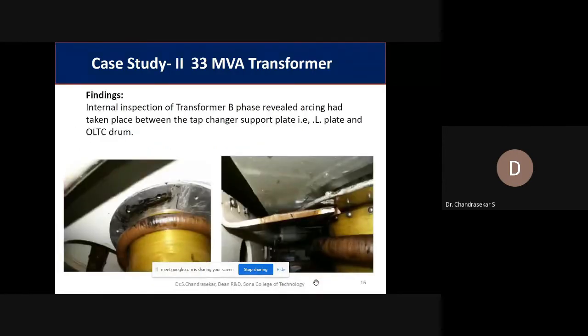This is another case study of the same 33 MVA transformer. It has 3 phases, and in phase B, we found an L plate, the tap changer support, and the OLTC drum. In between those, continuous arcing happened.